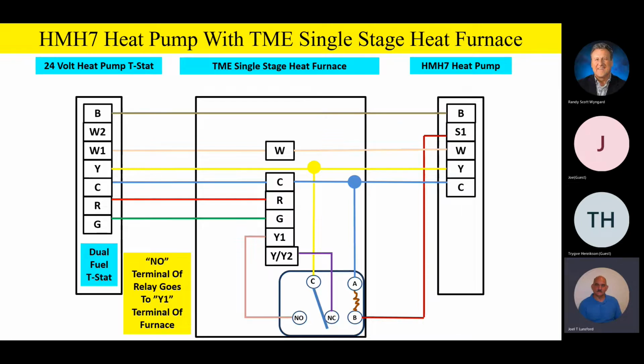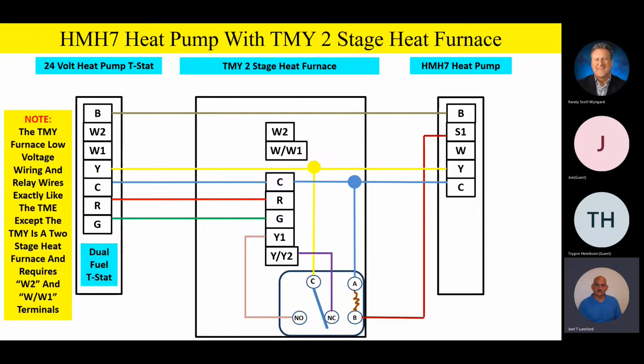Excellent answer. Any other good questions or comments before we continue? If we're good, okay, team, here we go. Let's take a look at a TMY 2-stage furnace. Please note the TMY furnace low voltage wiring and the relay is going to wire exactly like the TME furnace that we just discussed. The only exception is the TMY is a 2-stage furnace and requires a W2 terminal. As we take a look at it, there's a slight terminal change. It wires exactly like we had before.